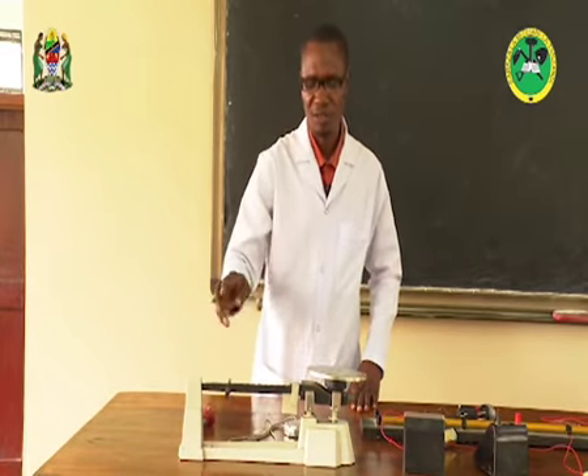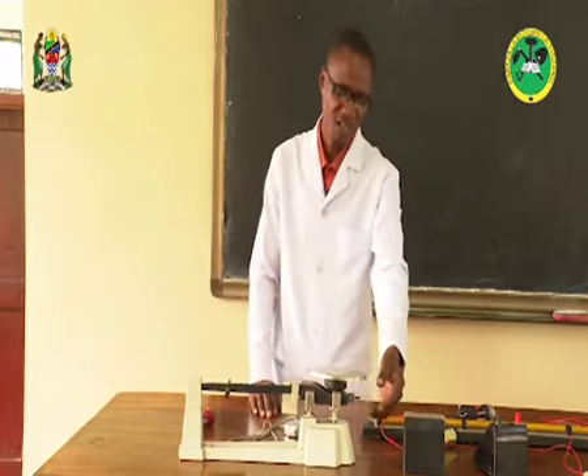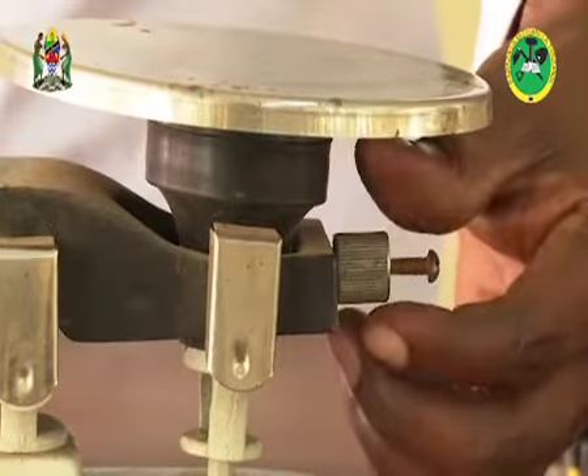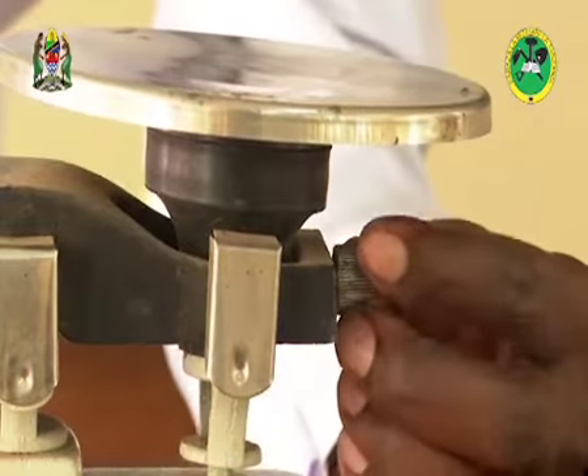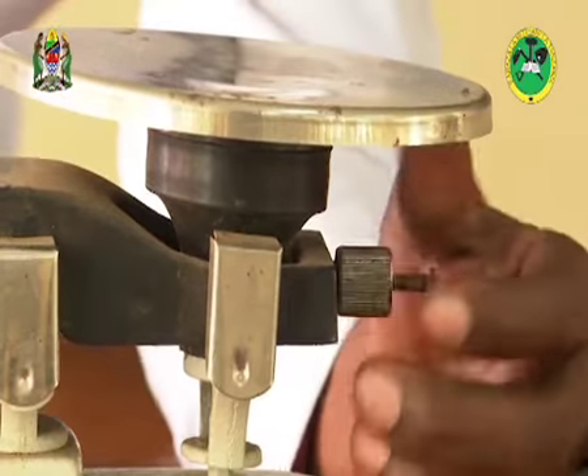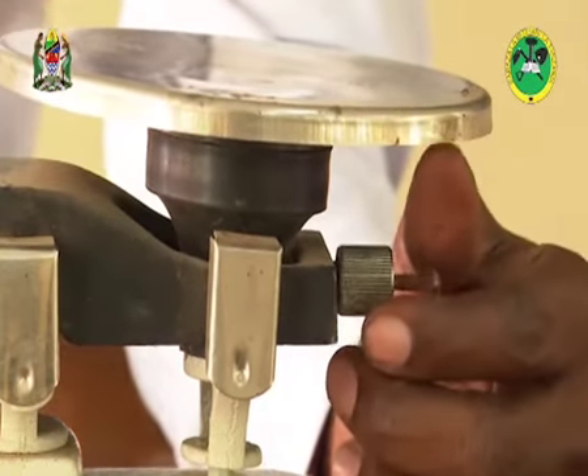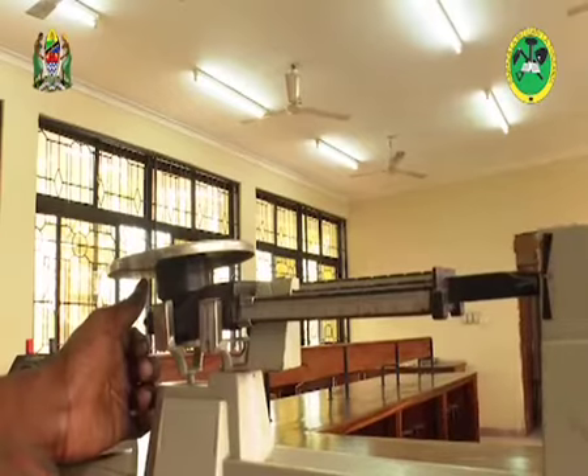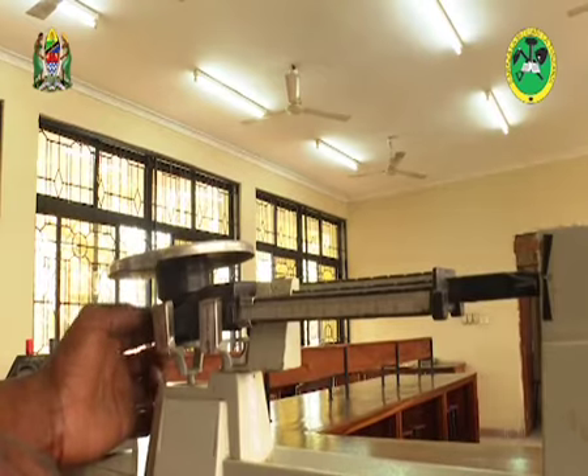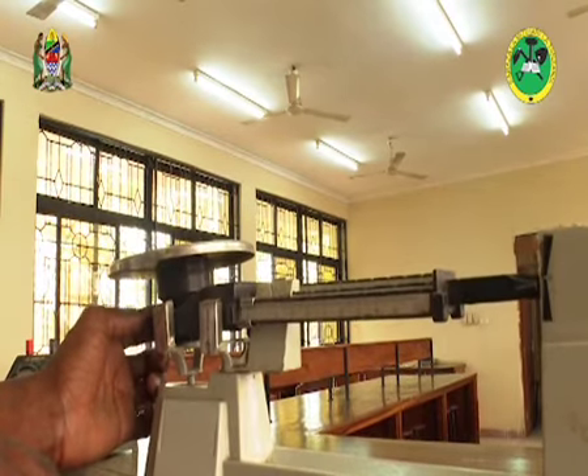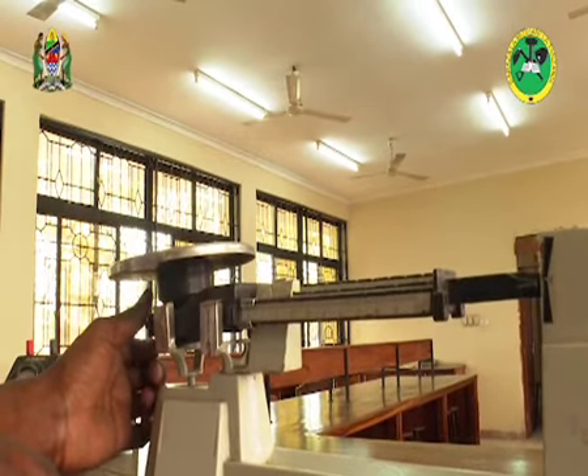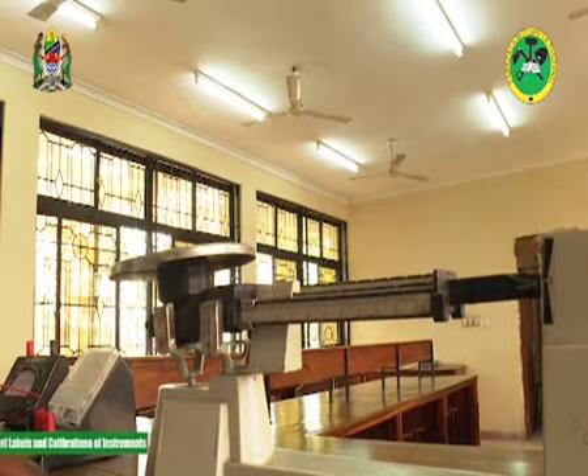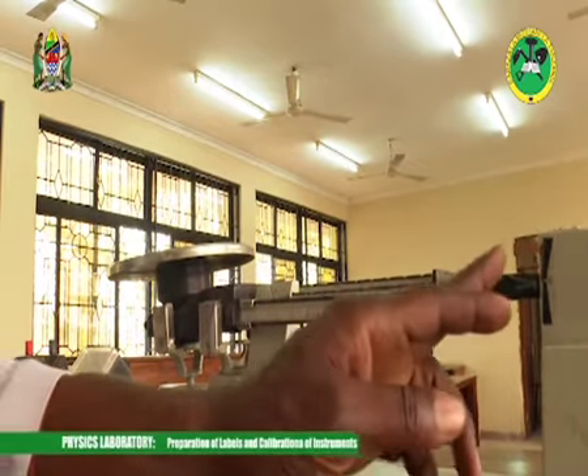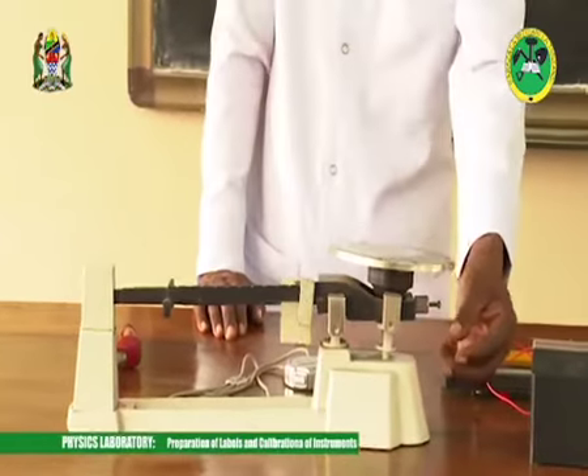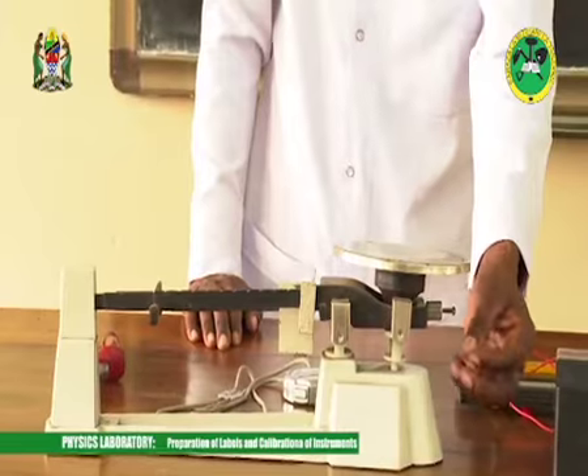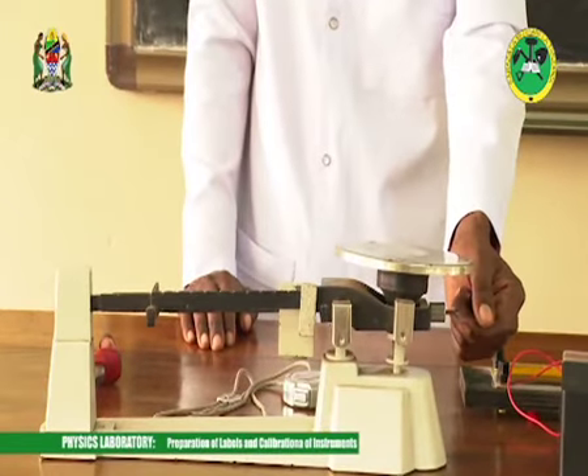If it's not pointing, you have an adjustment knob here at the rear side, at the back side here, which is free to turn clockwise or counterclockwise. So your purpose is to roll it or adjust it clockwise or counterclockwise till, when you suspend it freely, you can find that this mark is always pointing at a 0 position by using this adjustment knob. We will showcase how we adjust this.